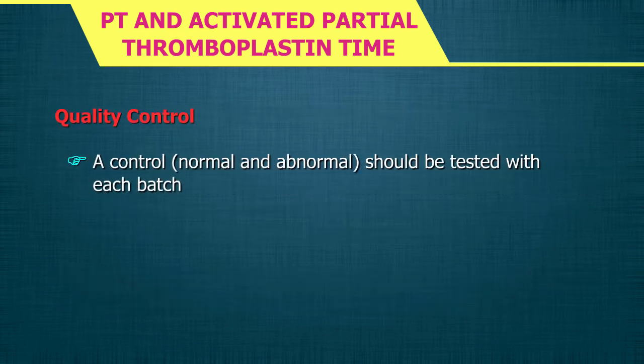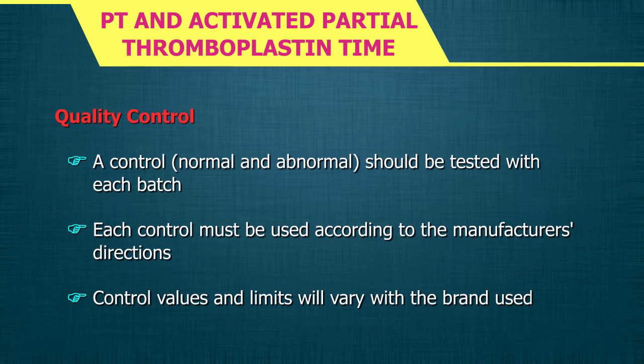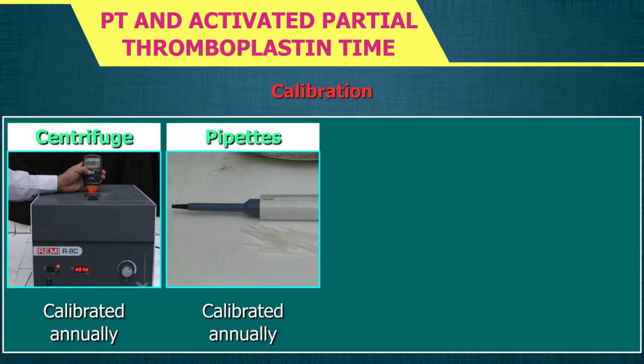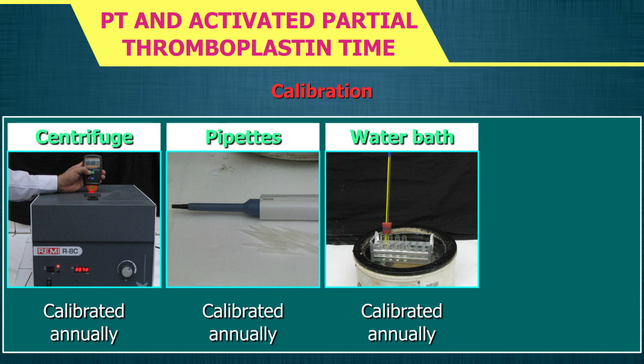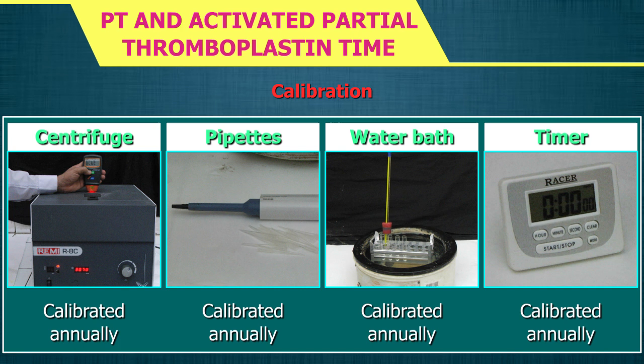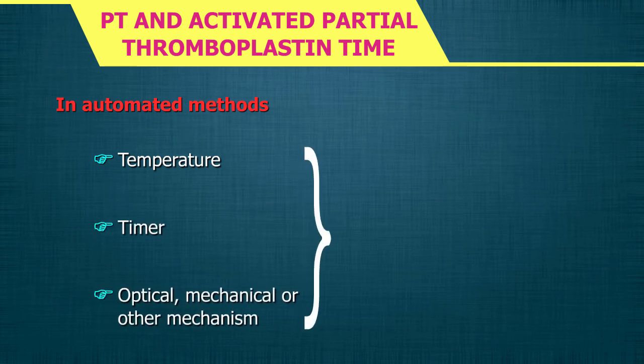For quality control, a normal and abnormal control should be tested with each batch, according to the manufacturer's directions. Control values and limits will vary with the brand used. For calibration: the centrifuge used for PPP, the pipettes, the water bath for manual methods, and the timer should all be calibrated annually. Multiple areas of the water bath should be calibrated for operating temperature. In automated methods, temperature, timer, and optical or mechanical mechanisms of testing should also be calibrated.